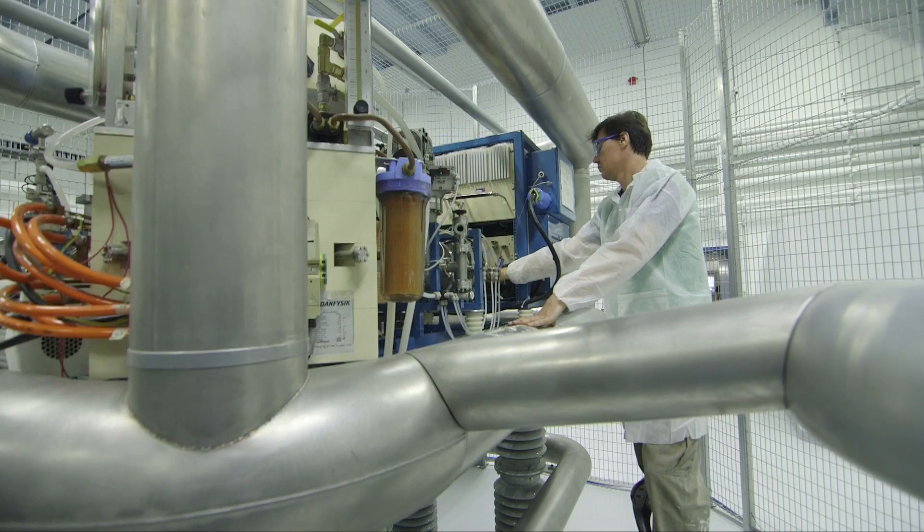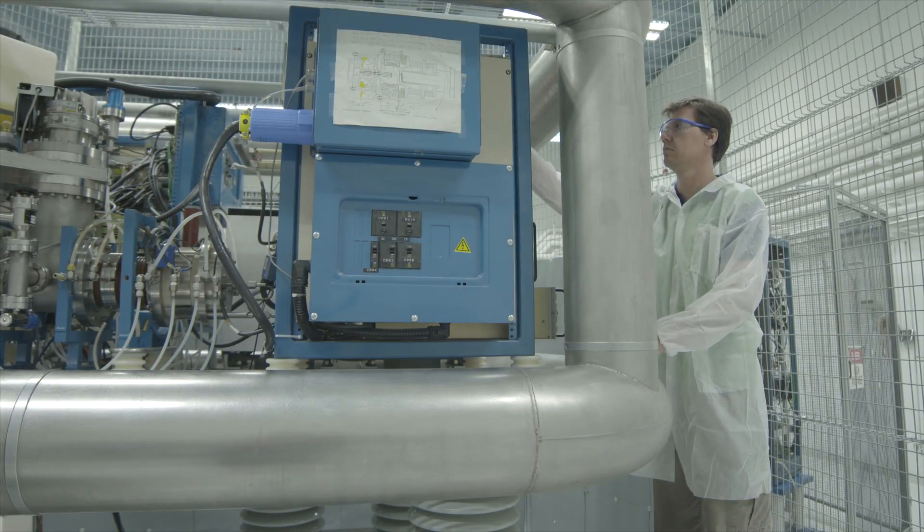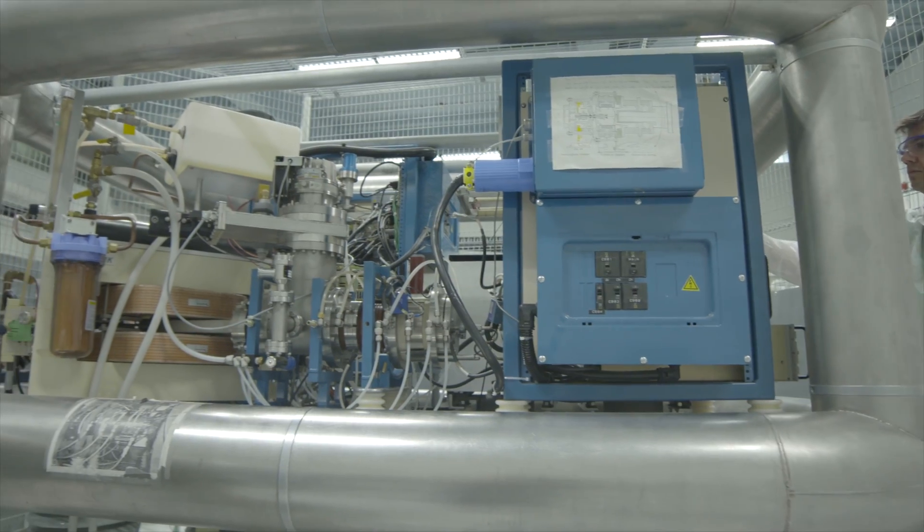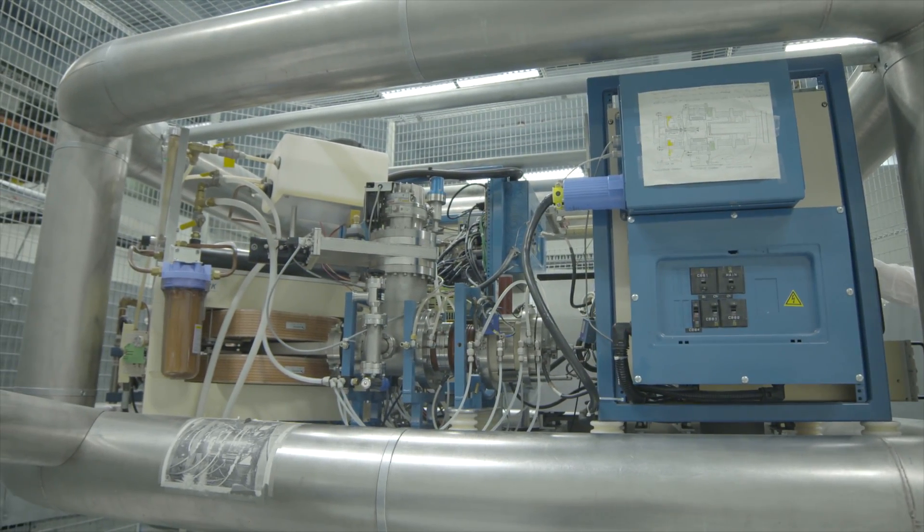The Danfysik 921A ion source can operate in three modes: gas with direct feed, liquid from vaporization of volatile compounds, or sputter from a solid target.